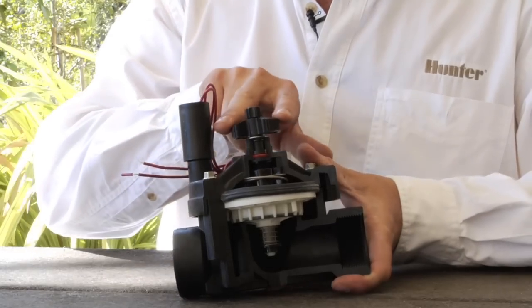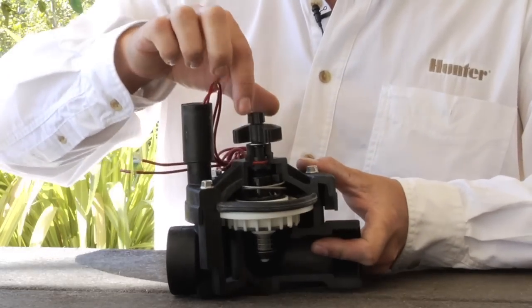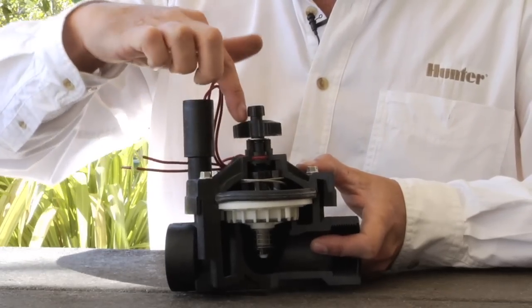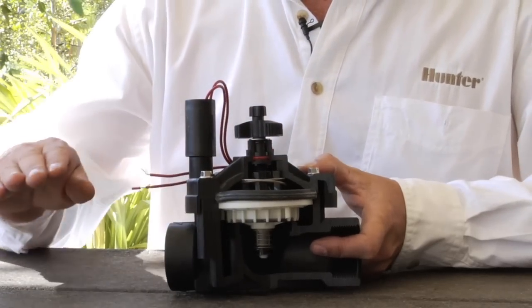On top of the flow control screw, we have what's called the manual bleeder screw. And opening the manual bleeder screw allows the water to evacuate out through that hole, and it allows the diaphragm to open, thus the valve will open with it.